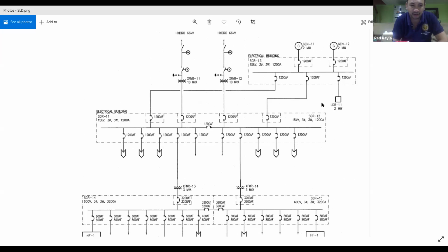Maybe we can throw the question to Engineer Nograles. Our typical systems in the Philippines maybe utilize 66 kilovolts down to 22 kilovolts, sometimes 34, 33 kilovolts, down to 440 volts at the medium voltage. Does that necessarily make a good comparison to the Canada electrical system? Do we have any problems having that configuration? We don't have the same configuration as you have right now. Your 15 kV might be, on our side, 21 to 22 kV down to 440 volts or 380 volts. What can you say about that, Engineer Nograles?